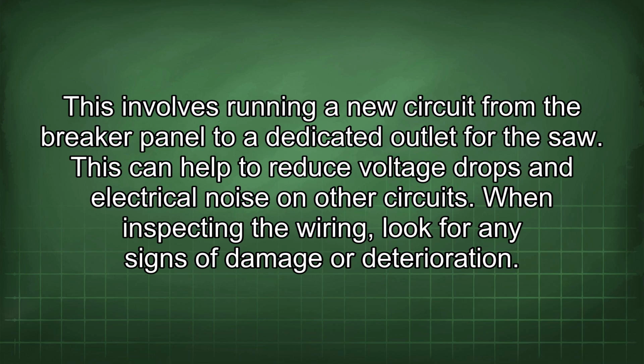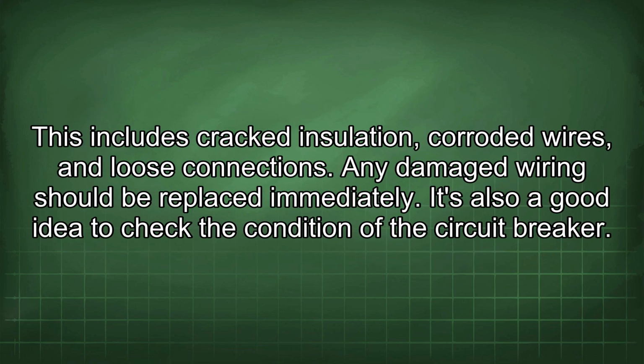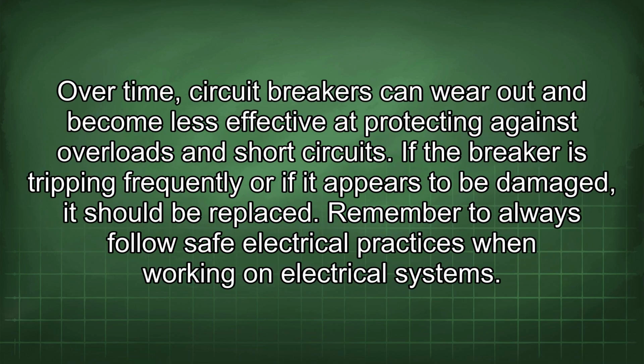When inspecting the wiring, look for any signs of damage or deterioration. This includes cracked insulation, corroded wires, and loose connections. Any damaged wiring should be replaced immediately. It's also a good idea to check the condition of the circuit breaker. Over time, circuit breakers can wear out and become less effective at protecting against overloads and short circuits. If the breaker is tripping frequently or if it appears to be damaged, it should be replaced.